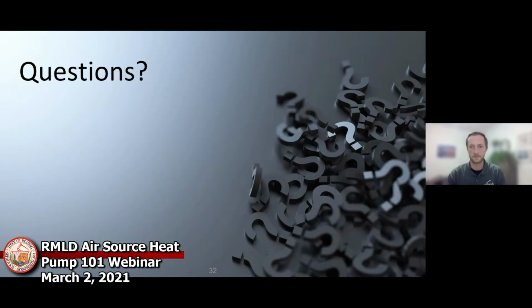Another question for you, Christopher. I know you touched on this a little in the presentation, but you mentioned heat load sizing versus typical general sizing. Is there a standard for what approved vendors should be doing to better size the system for your home? Yeah, specifically what it's called is a Manual J, those are heat load calculations. There's a lot of software out there that runs Manual J calculations. Then you can also run something called a Manual S to figure out what size equipment you should pick.